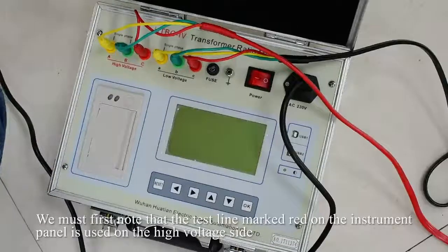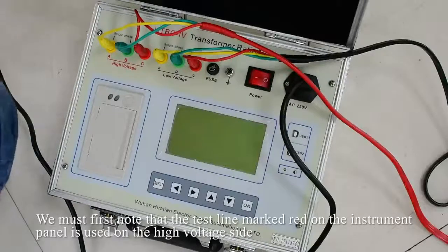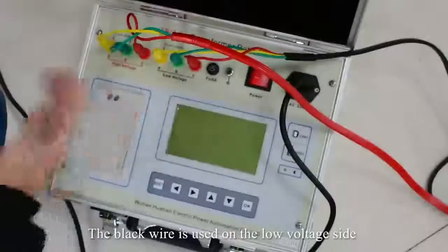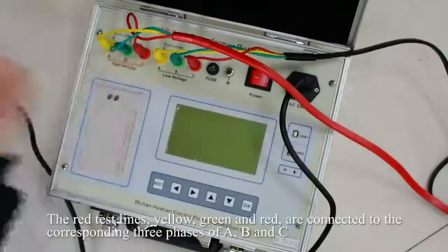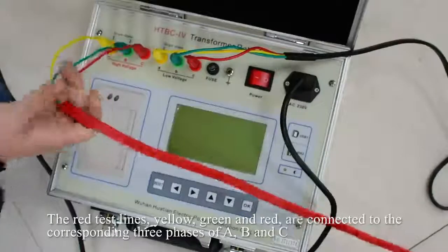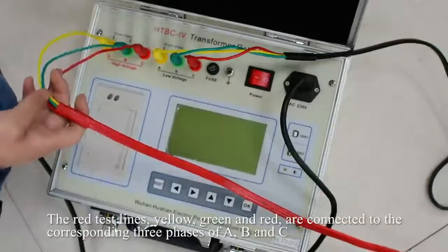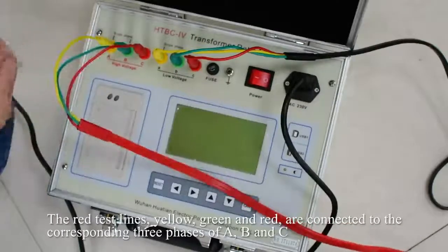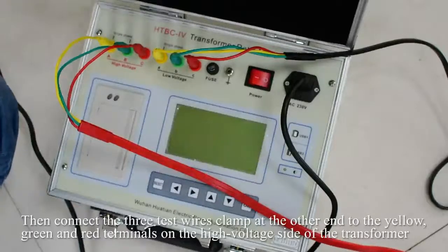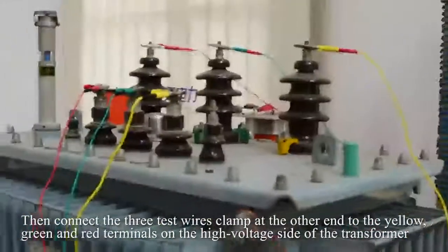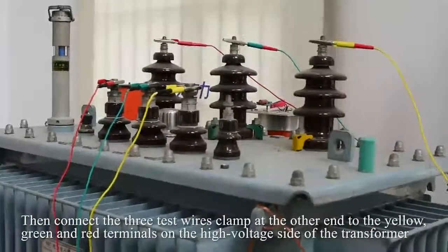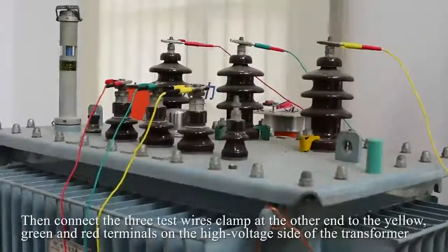We must first note that the test line marked red on the instrument panel is used on the high voltage side. The black wire is used on the low voltage side. The red test lines, yellow, green, and red, are connected to the corresponding three phases of A, B, and C. Then connect the three test wire clamps at the other end to the yellow, green, and red terminals on the high voltage side of the transformer.